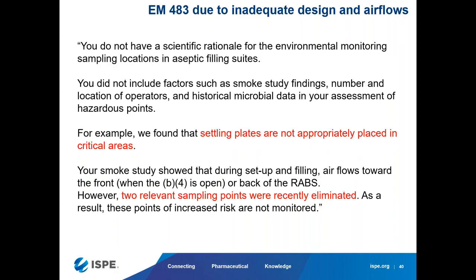Let's go to this. This is just becoming too much. This has been going on for 3 or 4 years: environmental monitoring, sampling locations. What they are saying is, we found that settling plates are not appropriately placed in the critical areas. And I told you the reasons why. If we do a risk assessment, we will come to know, oh my God, we have eddies here, we have deviant air, we have dead air here. And if we could understand that, we could have a good risk-based environmental monitoring program.